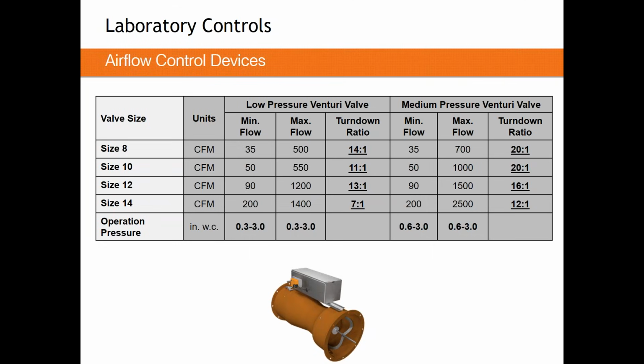Okay? So to get 700 CFM out of that valve, you do not need 3 inches. You don't need the maximum pressure to get maximum flow. If you have it, the valve will still work, but you can operate anywhere between minimum pressure and maximum pressure. You really can't operate outside that range at all, however. So if you have 0.5 inches, you don't have enough pressure to push that cone into the place where it's able to do its job. And if you have too much pressure, if you have over 3 inches, you're going to get some stack up. Basically, the spring inside that cone is fully compressed, and instead of being a spring, it's now a cylinder, and it's not able to meter that size orifice anymore. So we have to read this data differently. It's really critical that we do that.